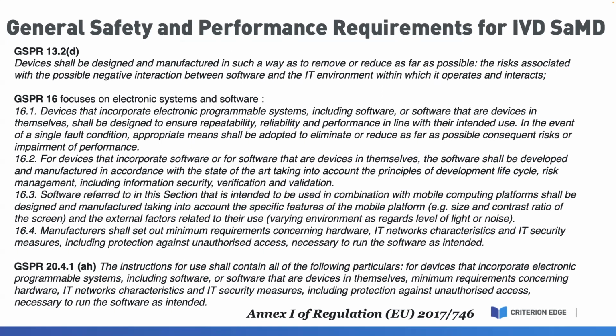And there are certain harmonized standards, though, that are directly relevant to software compliance. So, for instance, GSPR 13.2 requires devices to be designed and manufactured in such a way to remove or reduce the risks associated with negative interaction between the software and the IT environment in which it's operating.